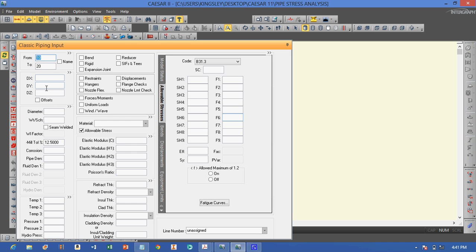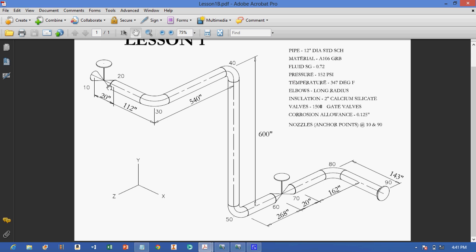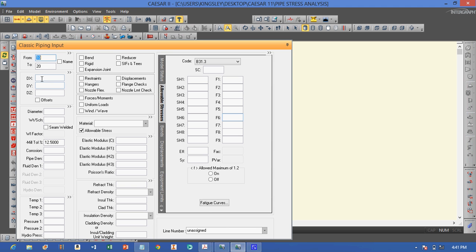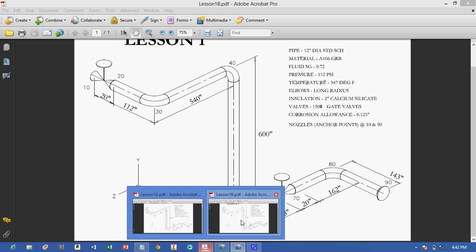From node 10 to 20, we have a gate valve, class 150 pounds, and the length is 20 inches in the X direction. We put 20 in the X direction. The diameter of the pipe is 12 inches, standard wall. The corrosion allowance is 0.125 inch, and the fluid density comes from the specific gravity of 0.7.